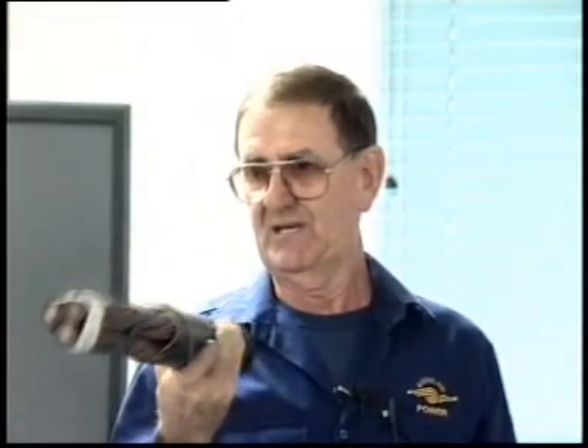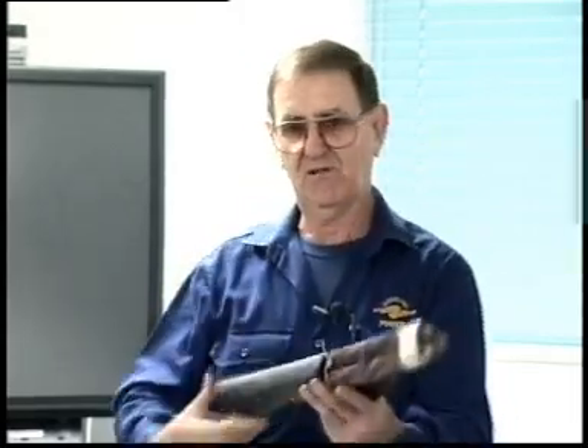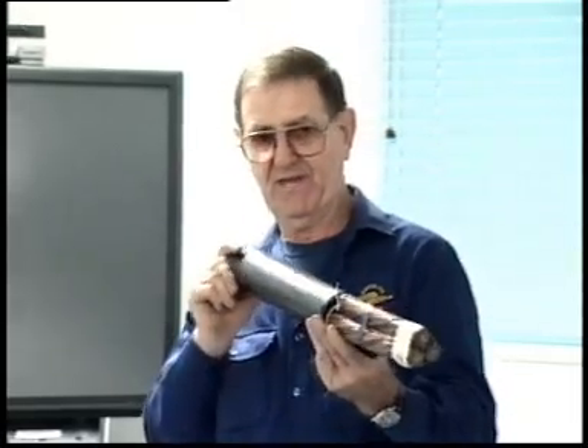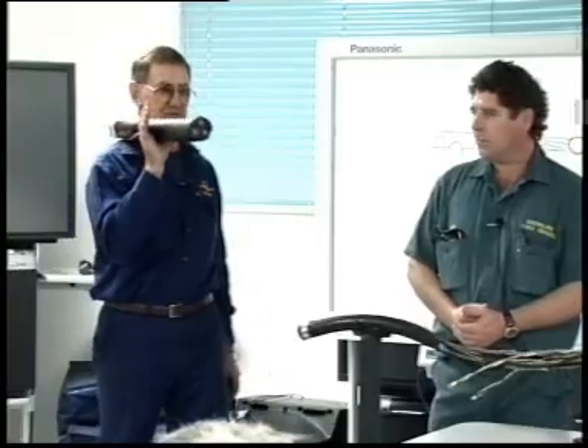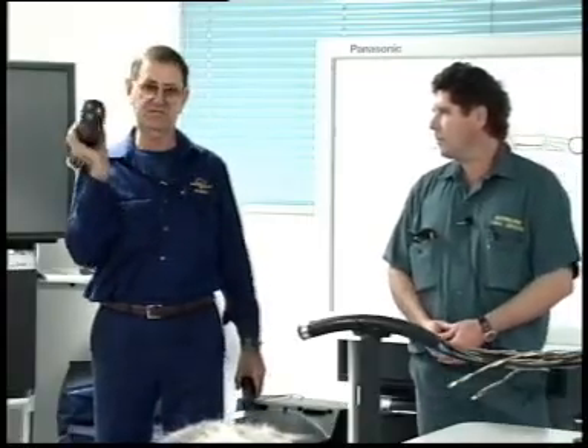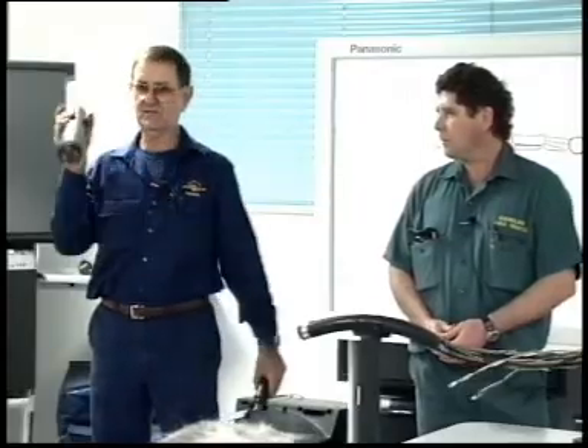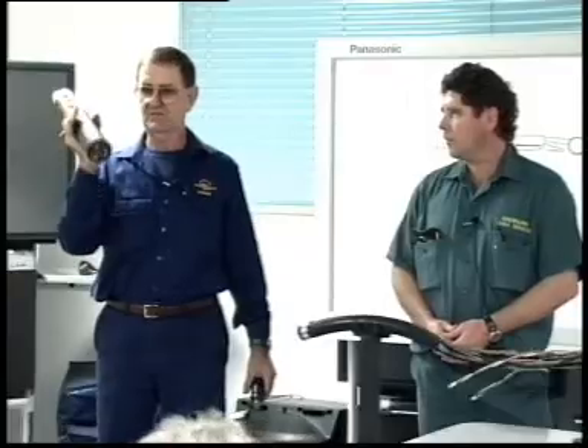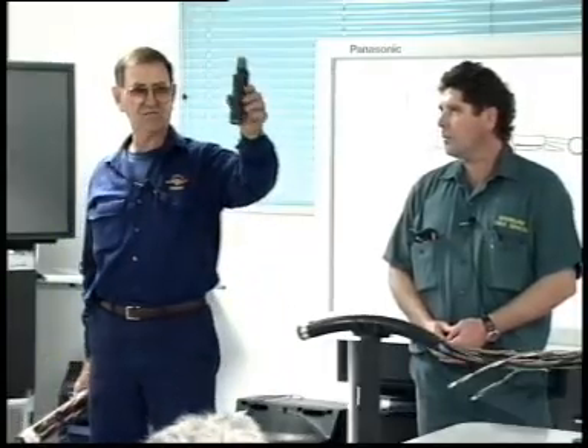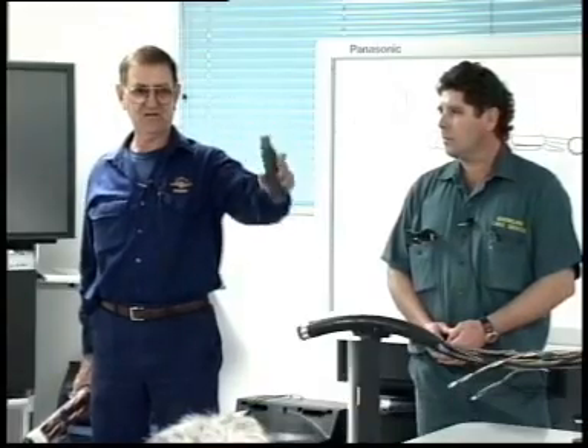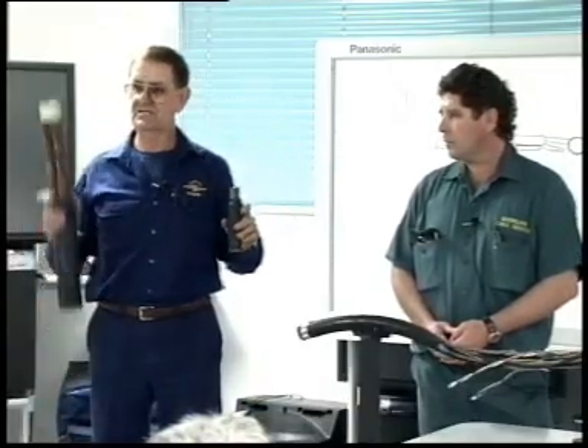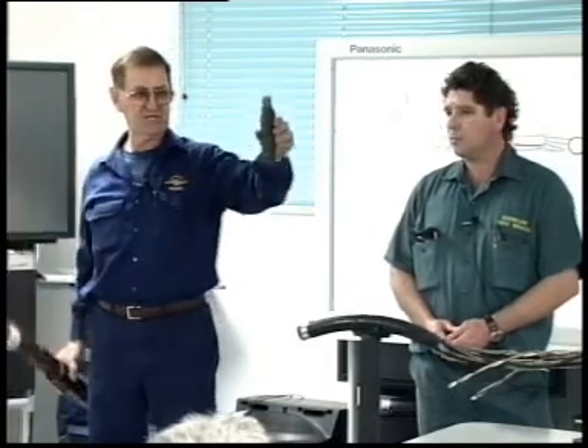Just this particular cable, as I said, they're updating the equipment that they're using on these. The insulation, the sheaths, the actual technology of the thing has gone ahead in leaps and bounds. And this cable here is more or less a replacement for that one there. So physically it is lighter, but physically it's a lot bigger to look at, and it's a lot stiffer, because of this new improved insulation. This one's a 22,000 volt cable, by the way. They make them in what we call a single core variety, which is like that, and power stations are starting to go to these now. They're doing away with their lead armours. Most power stations don't use a 3-core one like that. They use 3 single cores like that one there.